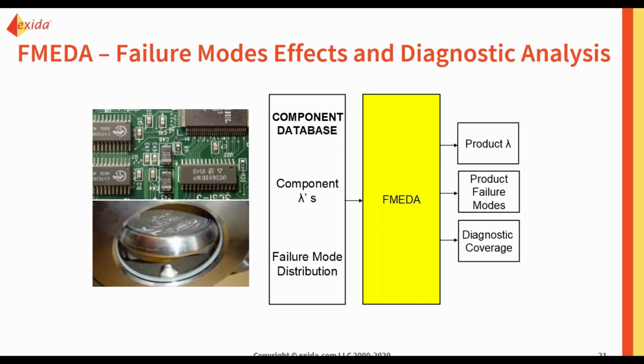And this is that detailed analysis of every single component of any given design. So we look at the exploded view or some sort of cutaway view where you can really see how the product works, and a detailed bill of material. And we go through every line of that bill of material and see how different stress that device will be seeing, how it handles that.